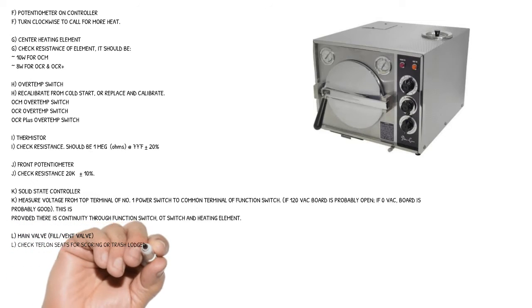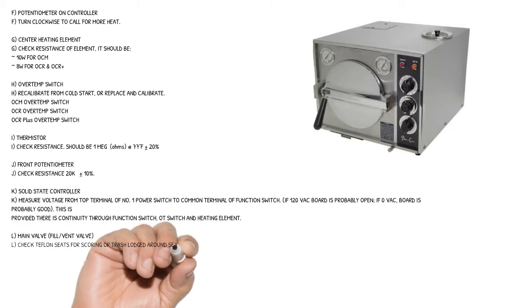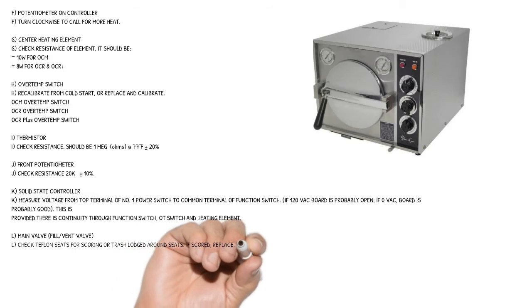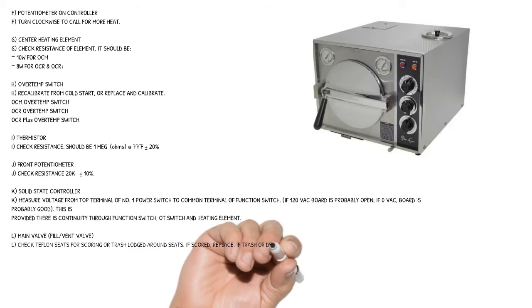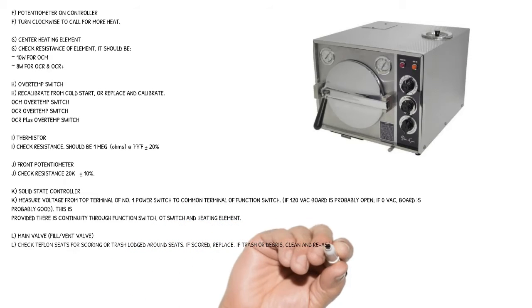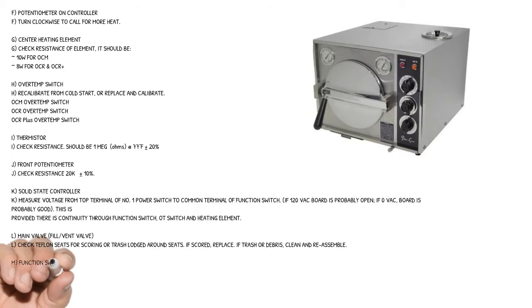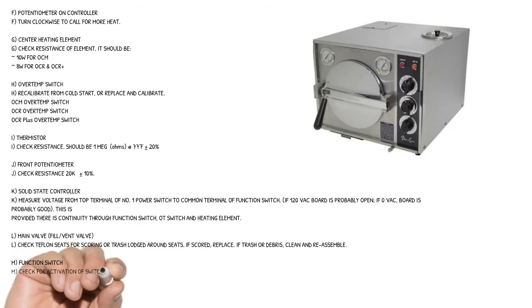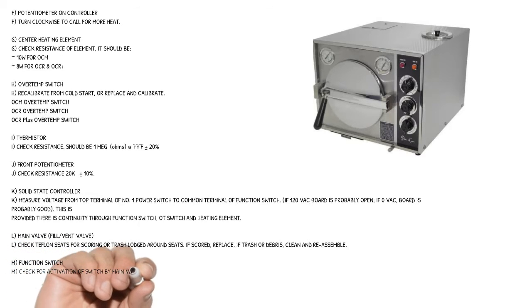Cause L: main valve, fill/vent valve. Check Teflon seats for scoring or trash lodged around seats. If scored, replace. If trash or debris, clean and reassemble.